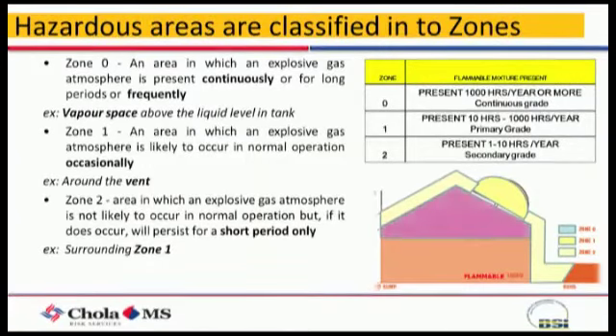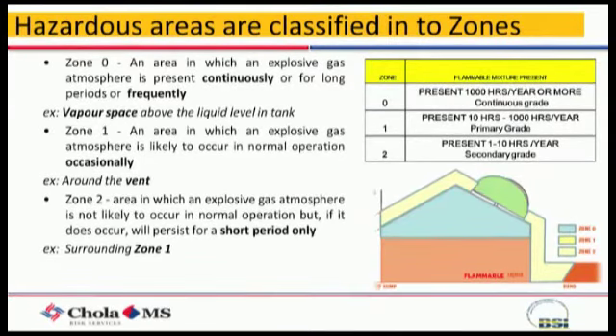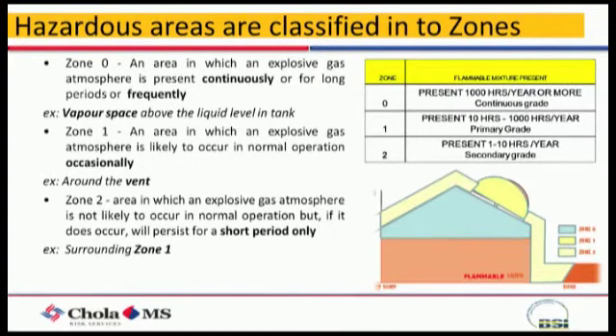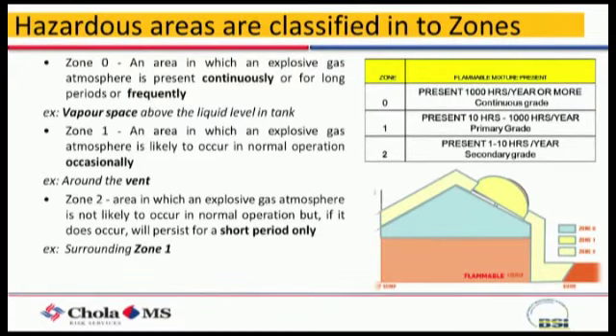Then what is zone 1? Take the tank or barrel's mouth opening — around the opening of the barrel, similarly around the small dipstick level where a daily monitoring reading is taken, an operator may stop and take a reading. For that, there's a small opening, maybe a level indicator or a manual hatch door to open and see, or for occasional cleaning where there are nuts, flanges and bolts. These areas around such openings are called zone 1, where vapor is not continuously present, but there's a chance of vapor occurring when it's opened. This happens more frequently, though not continuously — say weekly readings — and the accumulated hours in a year determine why it's classified as zone 1.